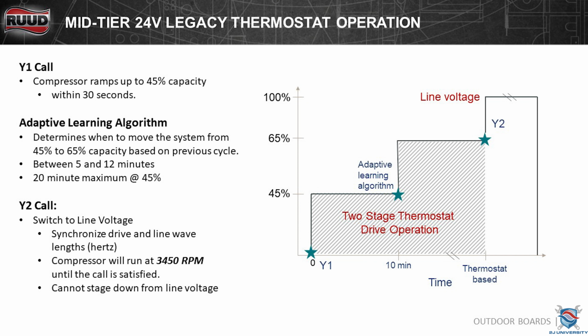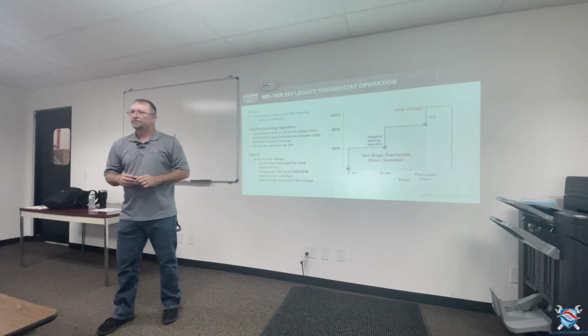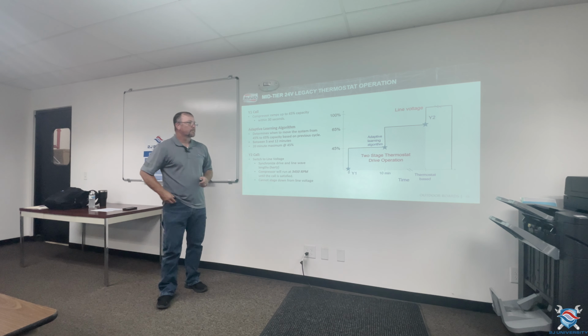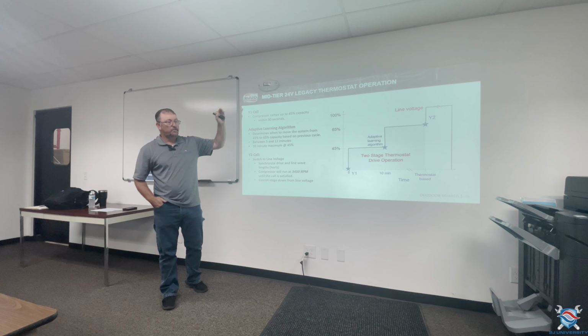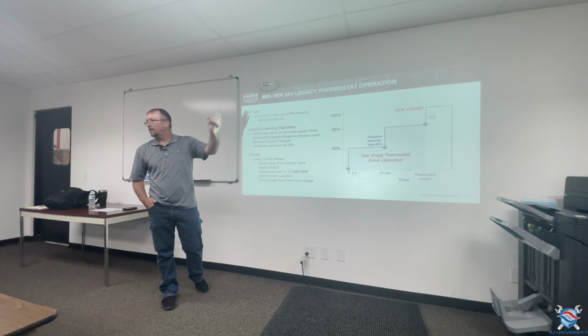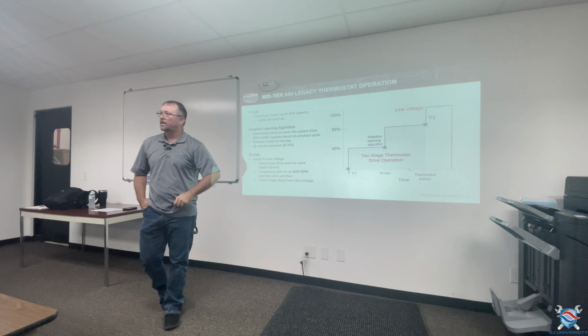Doesn't matter if you're in Econet or 24 volt, once it goes to 100%, it can never stage out of 100% and go back to either modulation or second stage, or middle stage if you want to look at it that way. That makes sense? Once it goes to high stage, it'll run at 100% in the call at 100%.